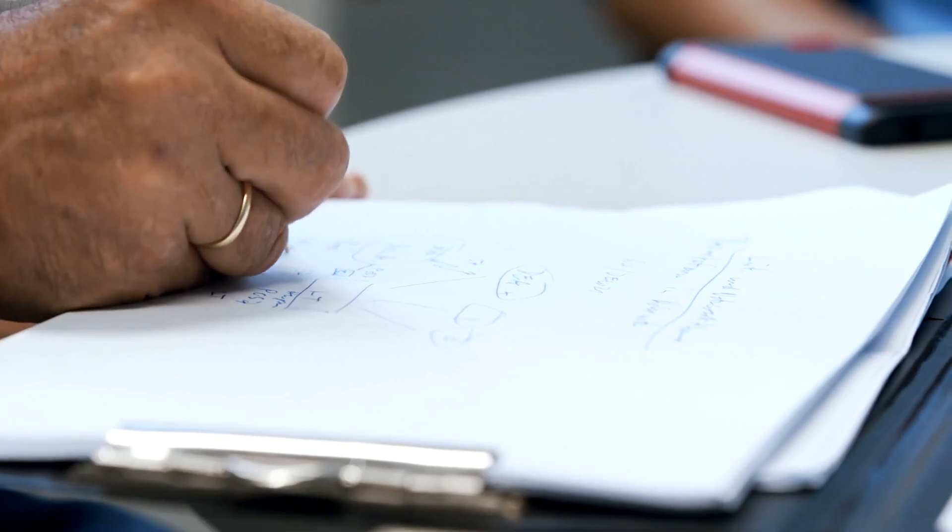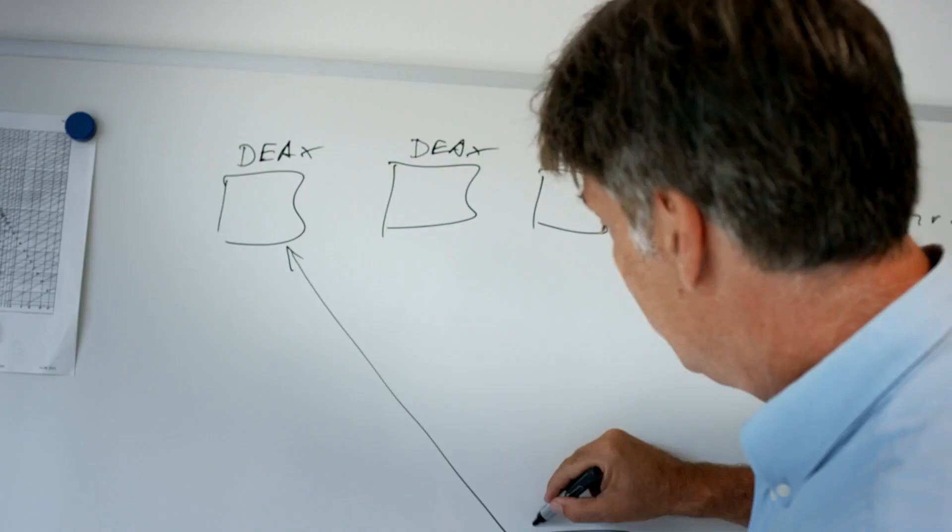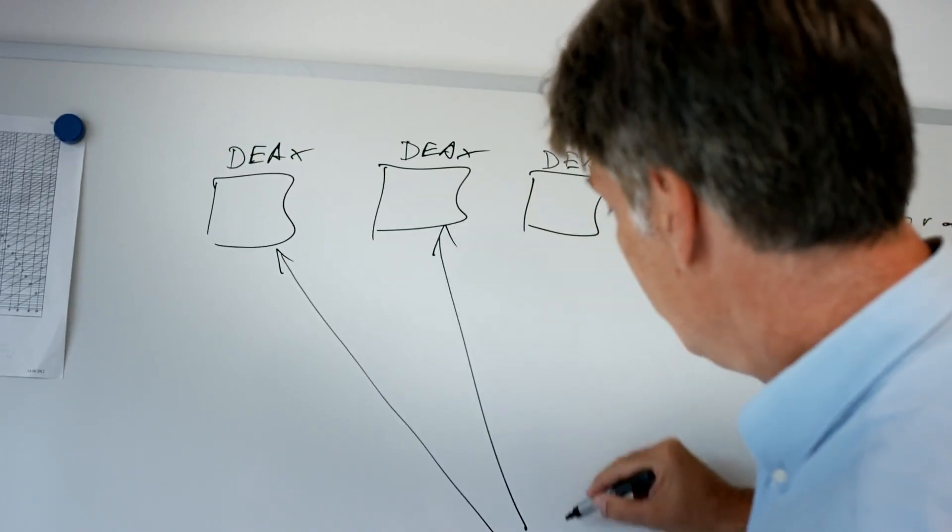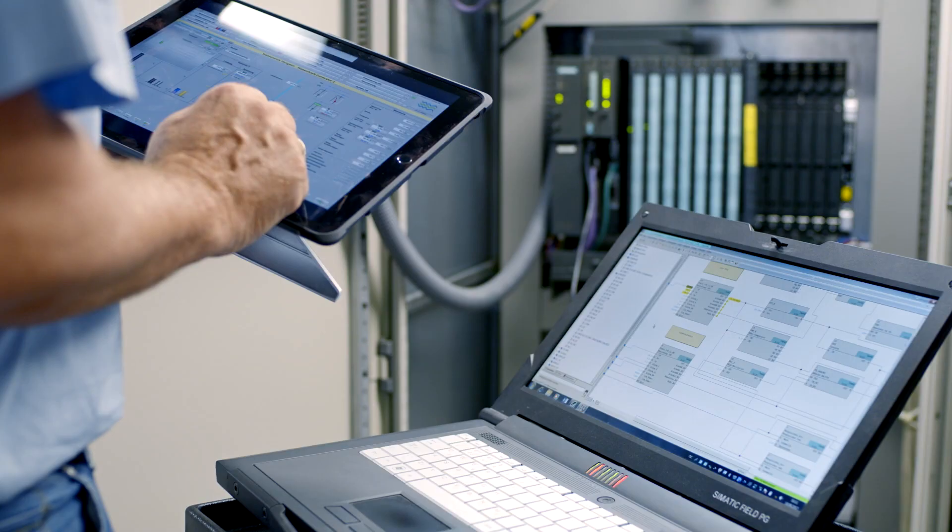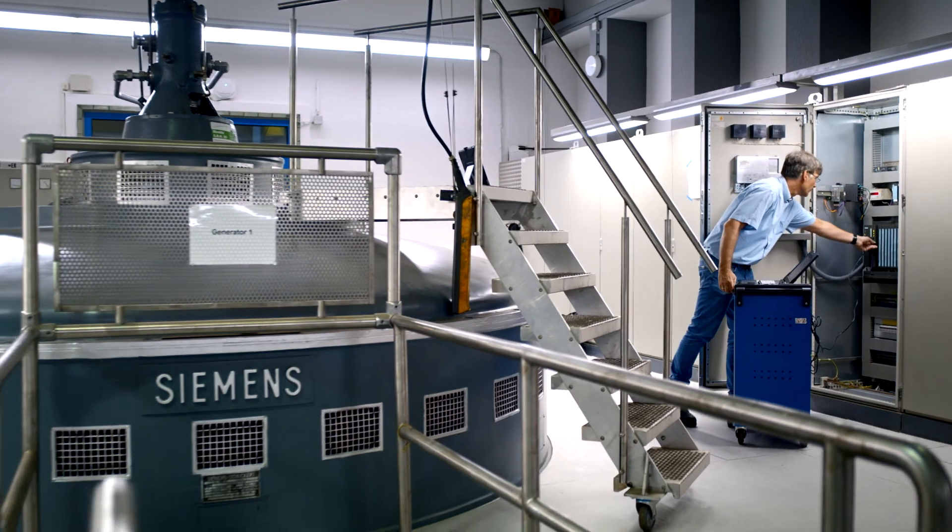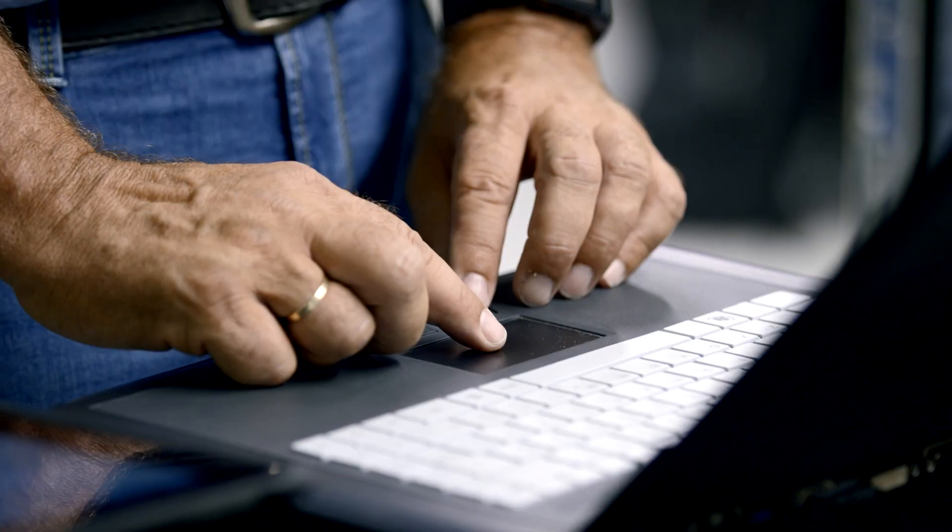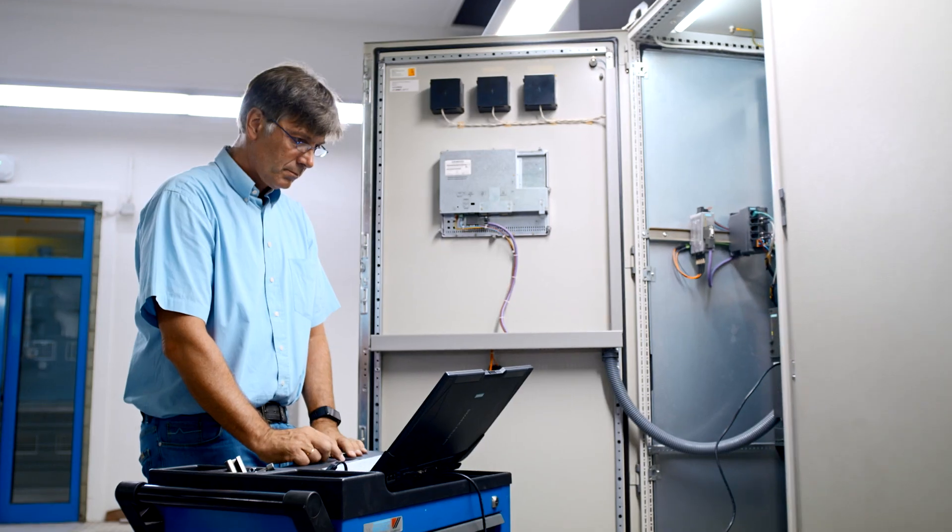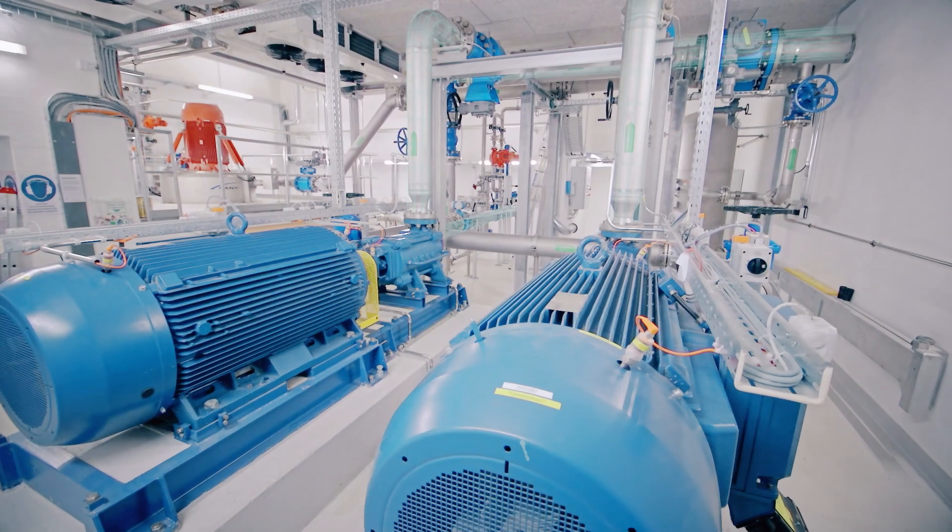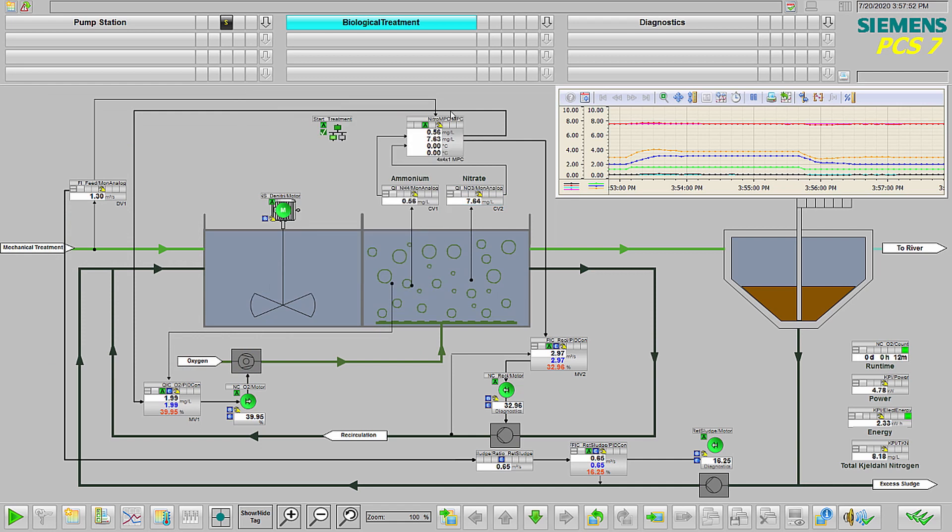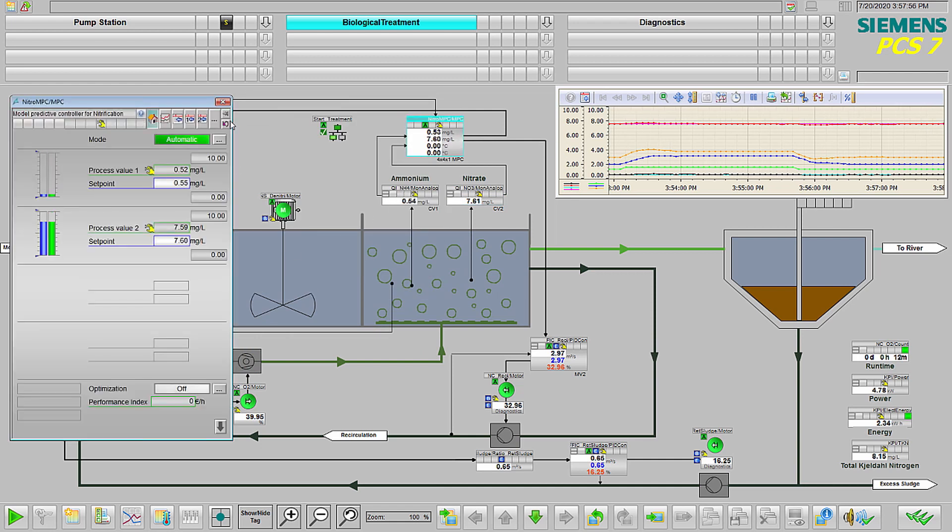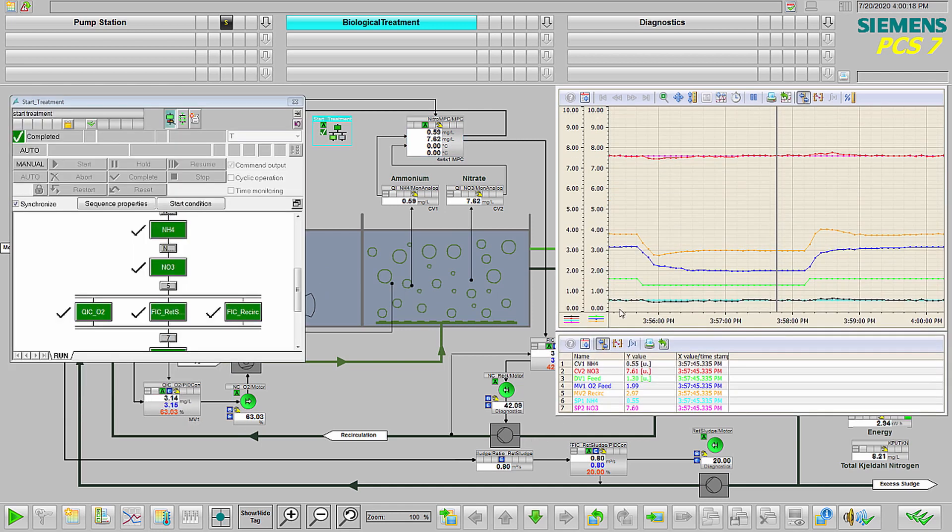You may be wondering how the model predictive controller knows what to do to optimize the operation. The model is developed by executing a series of bump tests. A control engineer introduces a measured disturbance to the process and trends how different process variables respond to the change. The resulting algorithm is stored in the control system configuration and is executed in real-time in the controller operating the plant.